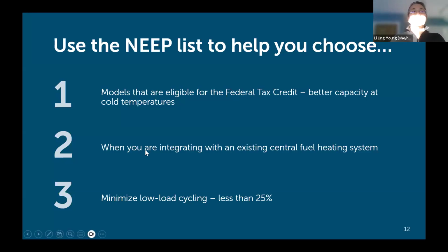You can also use the chart to size the heat pump if you know your customer will turn off the heat pump at say 20 degrees and just use their oil boiler. There's a feature where you can lock out the heat pump at 20 degrees, and then all your sizing is at 20 degrees instead of at -6 or whatever the design condition is in your space or town. Then it'll calculate how much energy the heat pump is going to use and how much energy the oil boiler is going to use. I think that's really clever. If you all have an easier way to do that that I don't know about, let me know, but the NEEP list is a place I think is really easy to get that information.